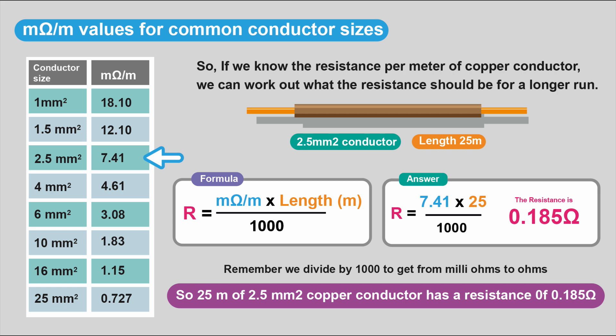So if we've got a 2.5 millimeter conductor of 25 meters, that's 7.41 times 25 divided by 1,000, and that will give us a resistance of 0.185 ohms. So 25 meters of 2.5 millimeter squared copper conductor has a resistance of 0.185 ohms.